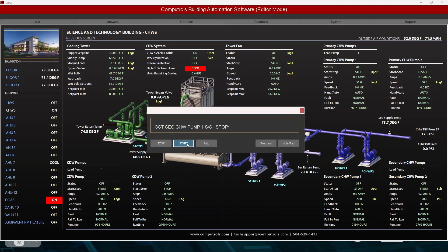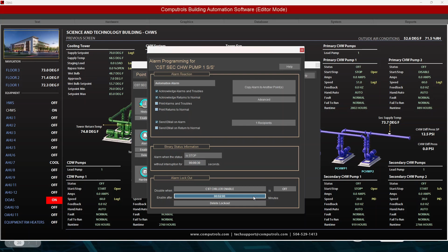Fill in the blank: alarm when the status is stopped without interruption for 30 seconds. How do I prevent false alarms? We use things like lockouts. If the chiller's off, lock out that alarm, I don't want to see it, and only enable it after the chiller's been running for 2 minutes. I can pick email recipients, etc. So as you can see, it's fill in the blank, easy to use stuff.